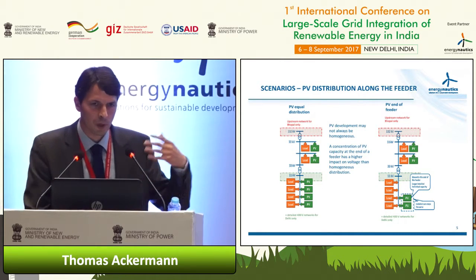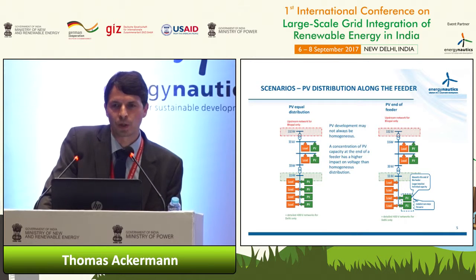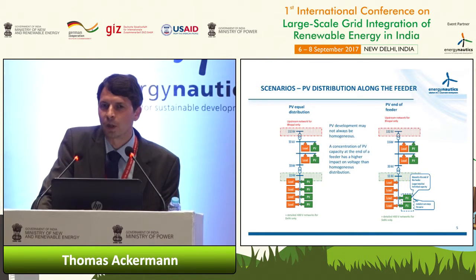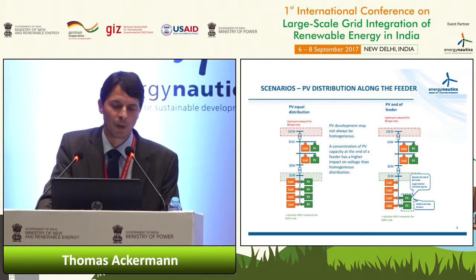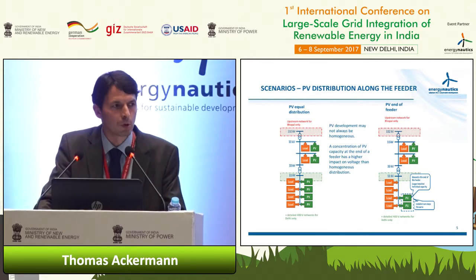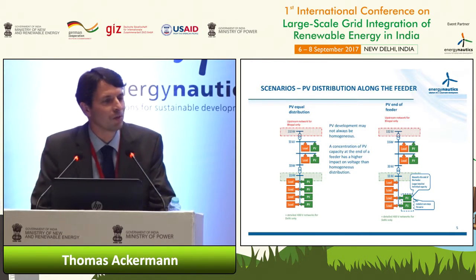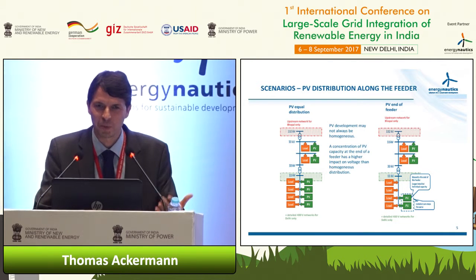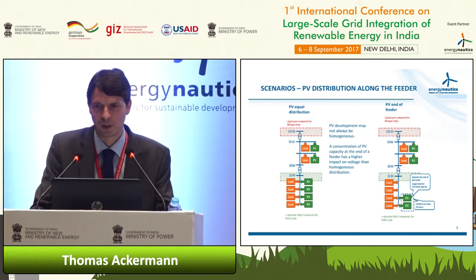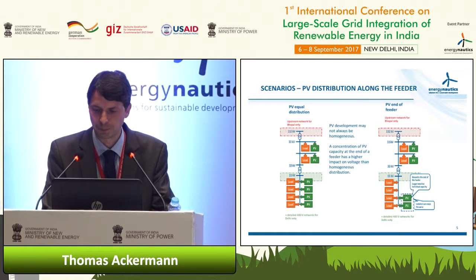If we talk about 100% PV penetration, that means 630 kW PV. On the rural side, we typically have 100 kVA transformers, so when we talk about 100%, we mean 100 kW of photovoltaic there.